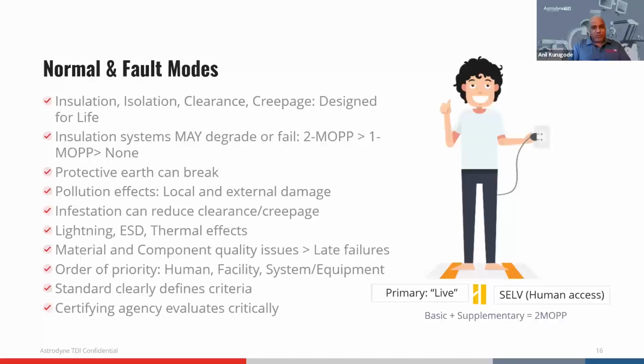Sometimes you can get hit by lightning, and then an insulation system can fail. But what happens when you have an insulation breakdown? Thankfully, the two-MOPP approach is your best insurance against shock, because if one thing breaks, the other one, which is equally good and meets the requirements, is there in place. That's the certification part of achieving two-MOPP.